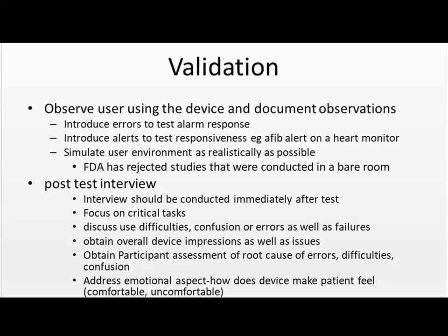We're going to simulate the user environment as realistically as possible. Now, that's an important point because the FDA has rejected studies that were conducted in a bare room where there was no attempt to simulate the user environment.